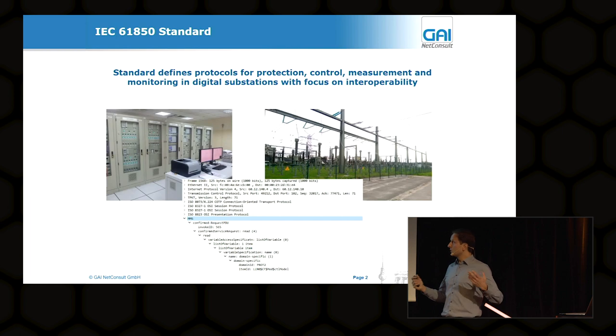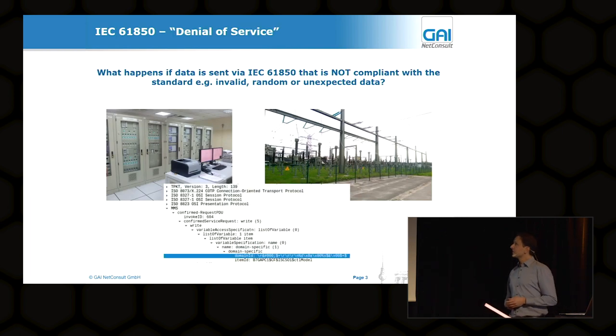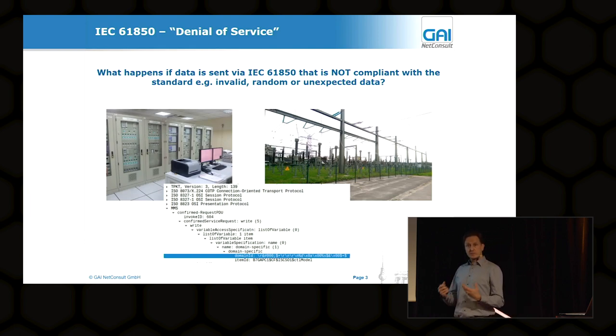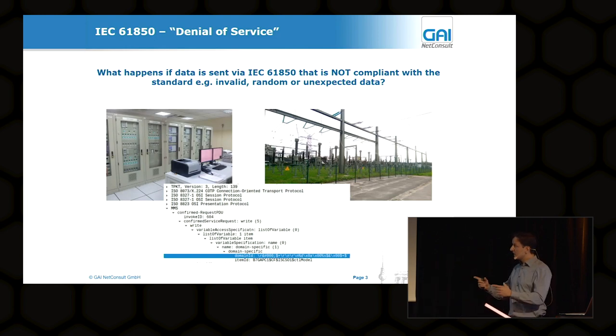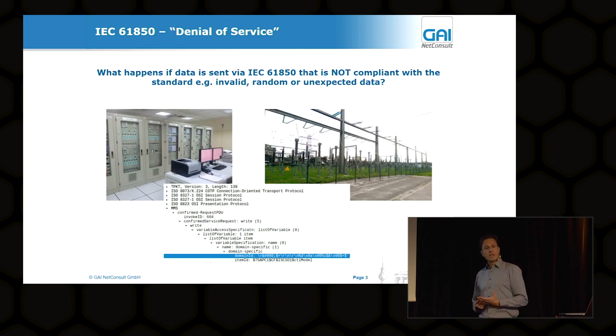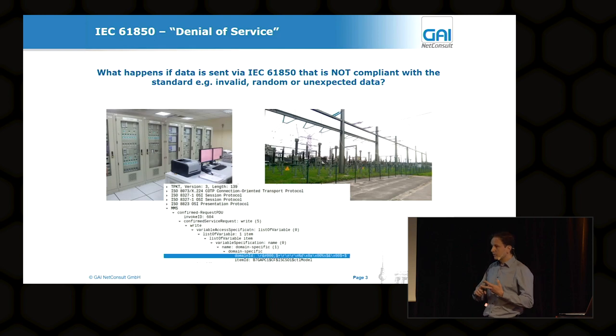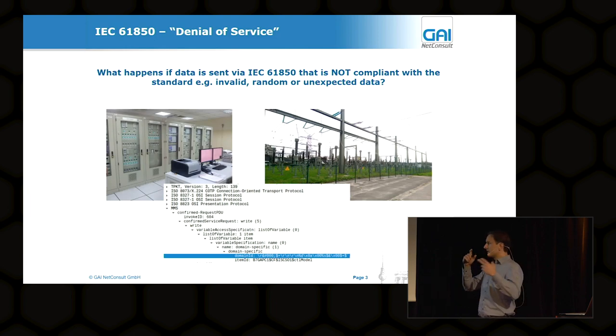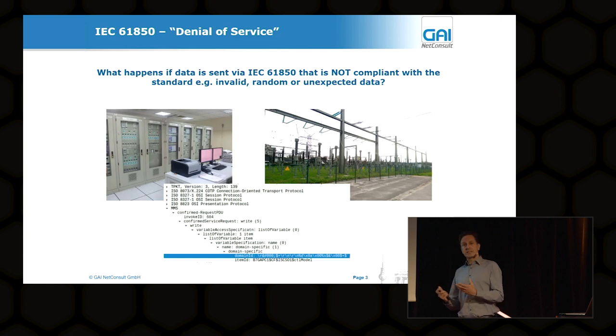We always encounter embedded devices in the substation, and a question comes up automatically: given such a complex protocol leading to very complex processing of IEC 61850 data on embedded devices with very limited hardware resources — limited memory, CPU, and so on — what happens if you send data via IEC 61850 that is not compliant to the standard? For example, invalid, random, or unexpected data — unexpected from a developer's point of view?